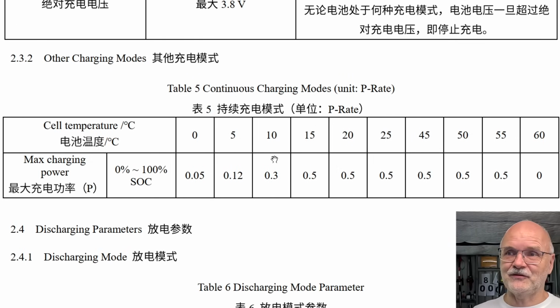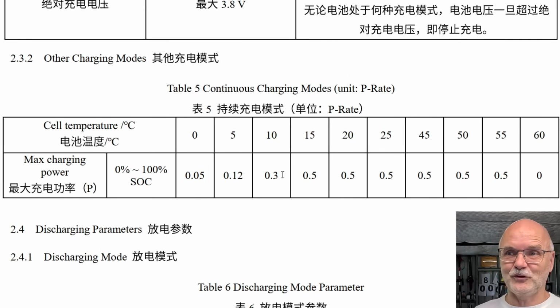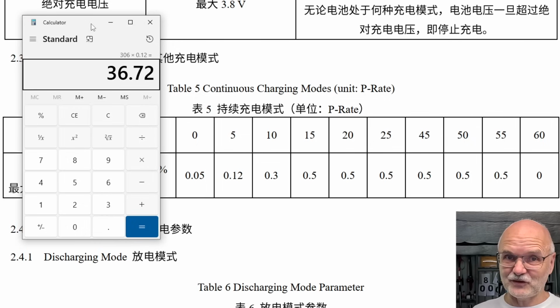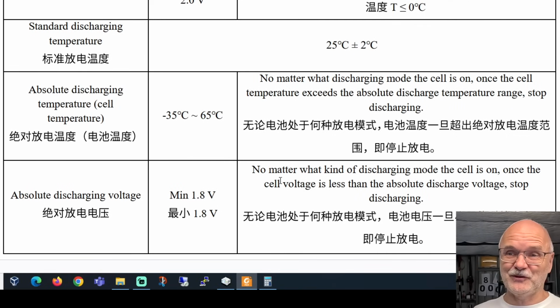At 10 degrees Celsius, we can only use 0.3 C. That is very interesting for cold winter days when your battery is ice cold. I mean ice cold with 10 degrees. And you are charging full speed into your battery. 0.3 is the maximum. At 5 degrees battery temperature, you can only charge it with 36.7 amps maximum. Look at this. And we also have an absolute discharge voltage of minimum 1.8 volt per cell now.